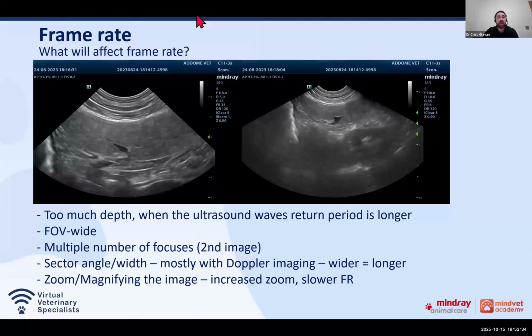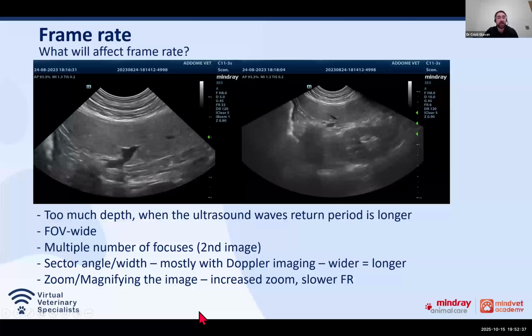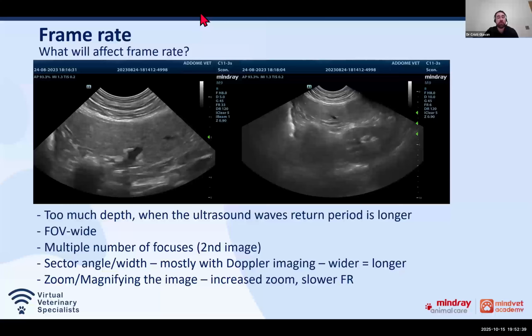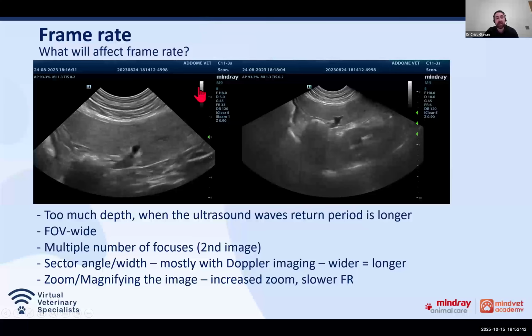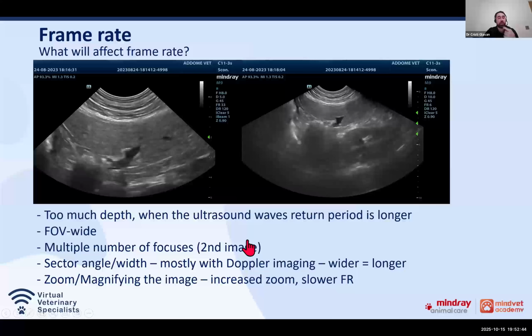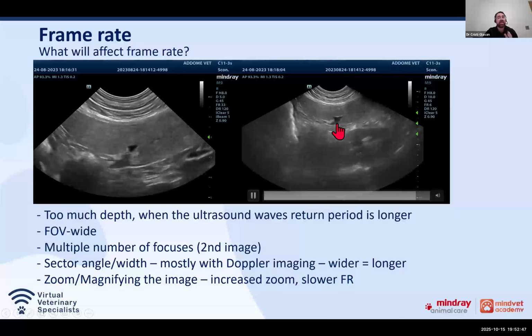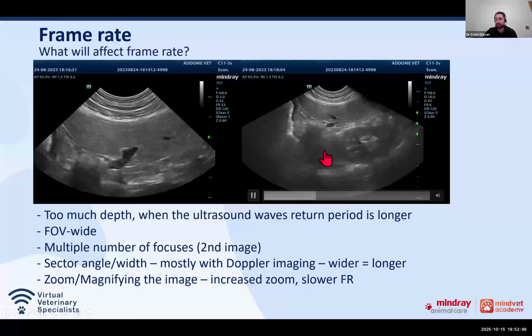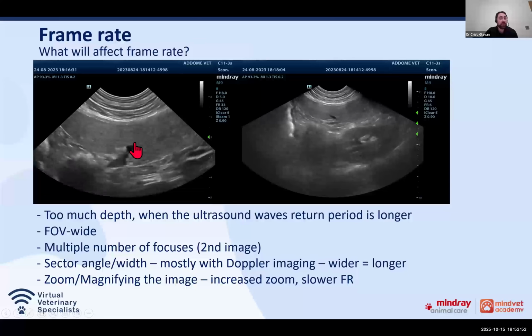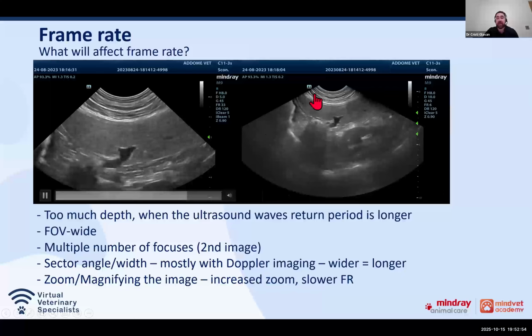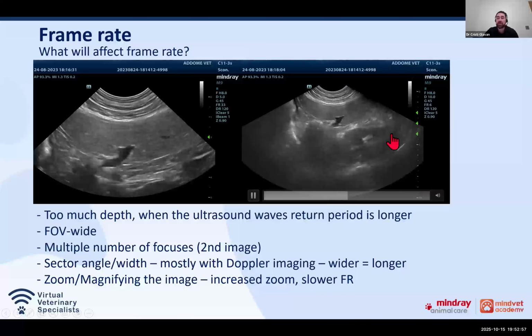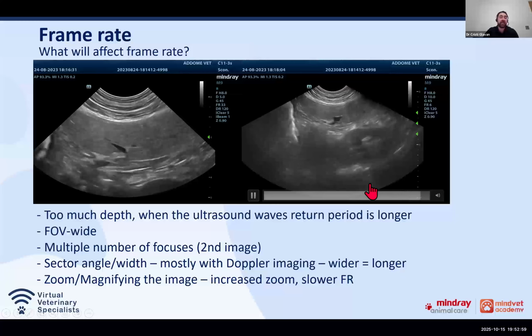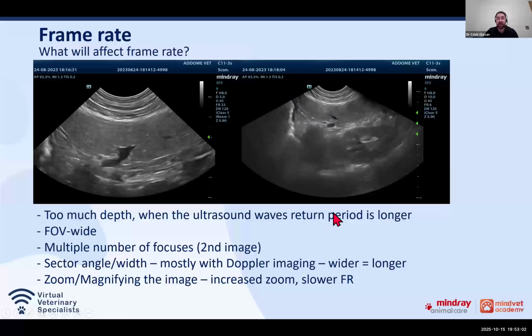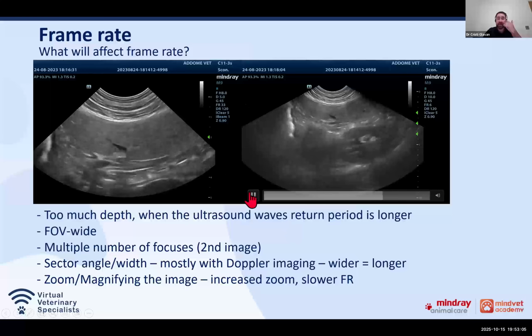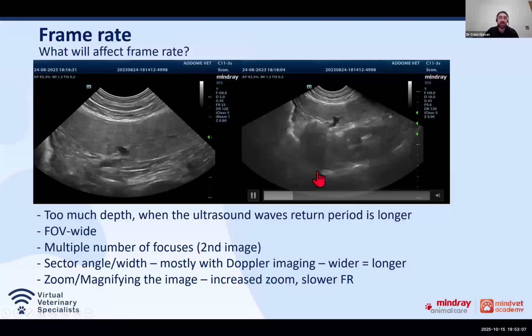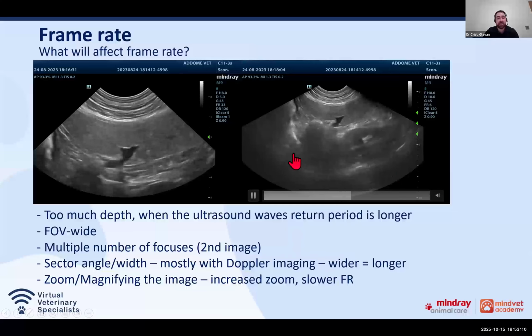Basically, all those ultrasound waves that we are sending at 10 centimeters deep, it will take another 10 centimeters to go back to the machine, and the machine will need to process that. So it will take longer for the machine to process all this information, and we might see a bit of a slow image. The field of view, if we have the field of view as it is here really wide, it will also affect the frame rate. Exactly, with the same principle that I have said earlier. Being a large area that we are scanning, it will take longer for the machine to process all those images.